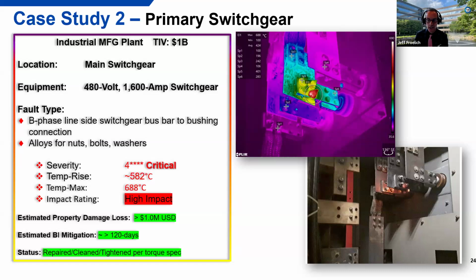And if you don't, you can have induction heating. You can have a gapping situation, and using a calibrated torque wrench and other techniques is crucial to making sure that the equipment is properly maintained and will receive good contact. The consequences are significant. You'll have heat generation, damage to wiring and bus. Resistance will restrict the current flow. You'll have a major potential for an arc flash condition, an unexpected, unplanned outage.